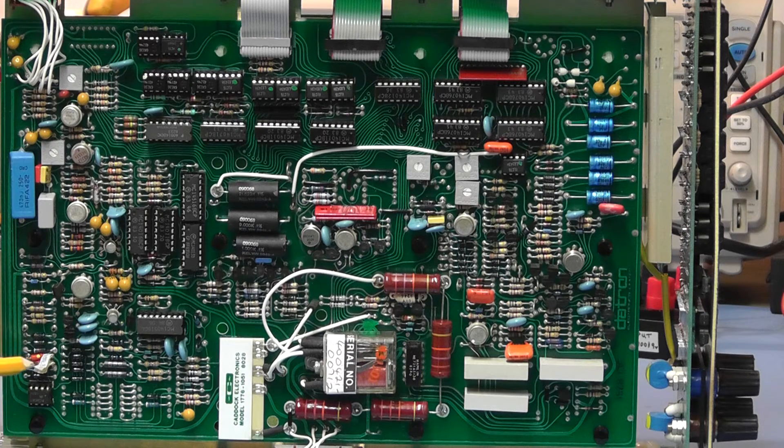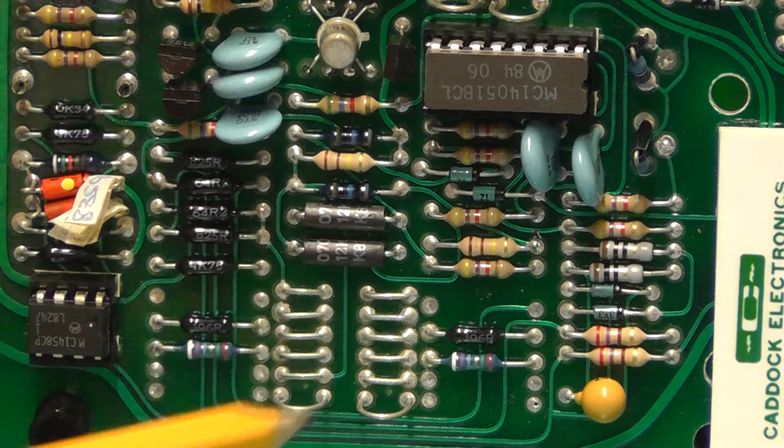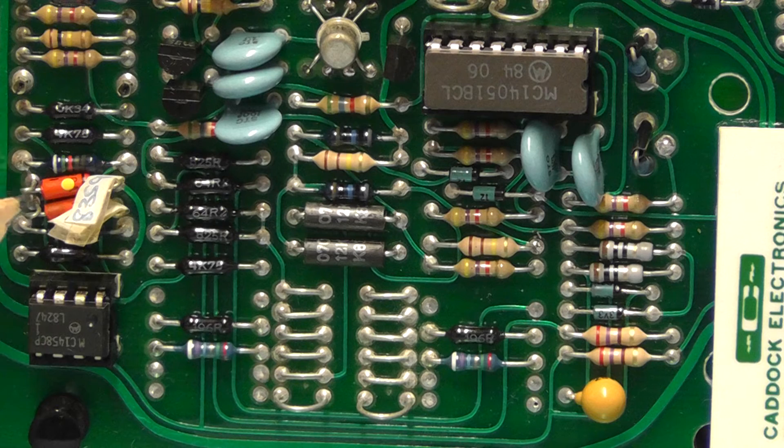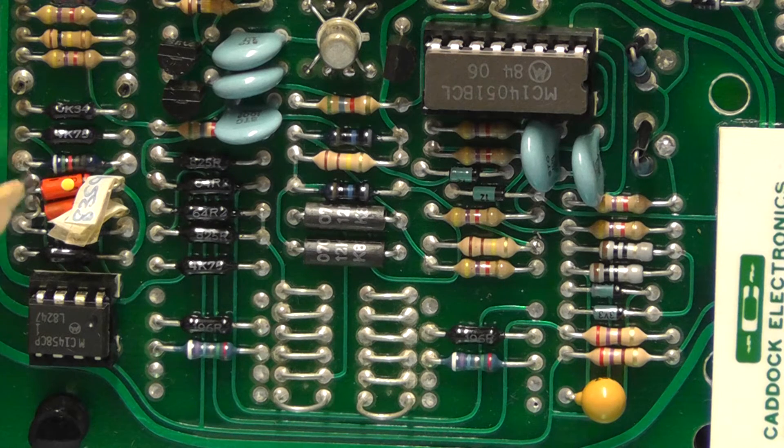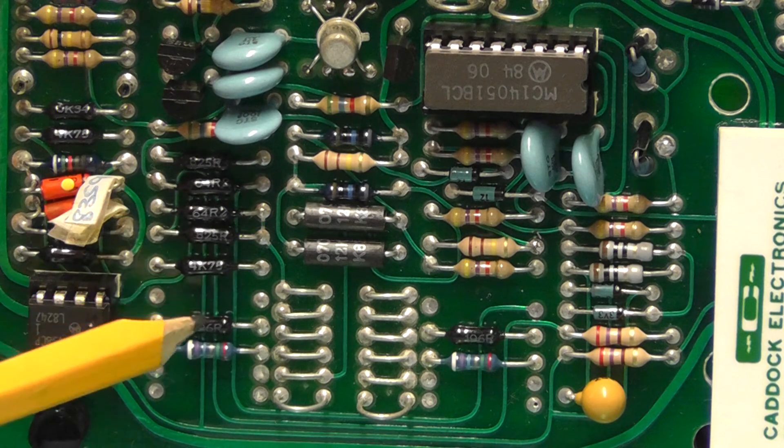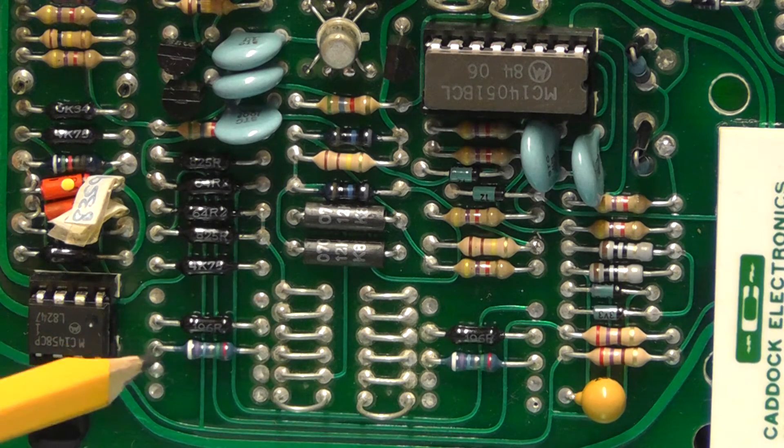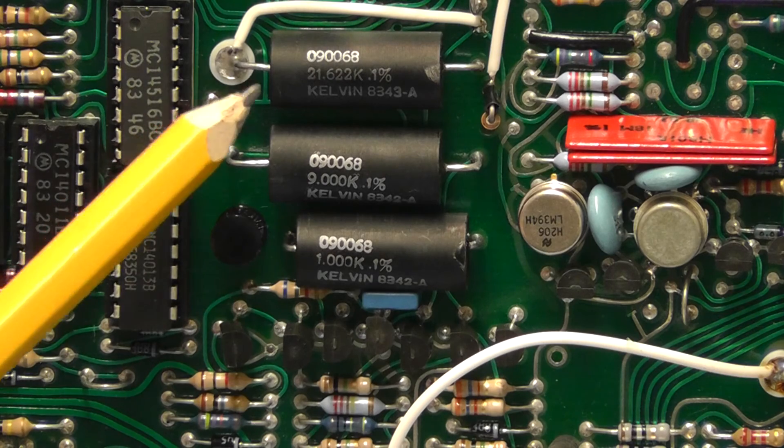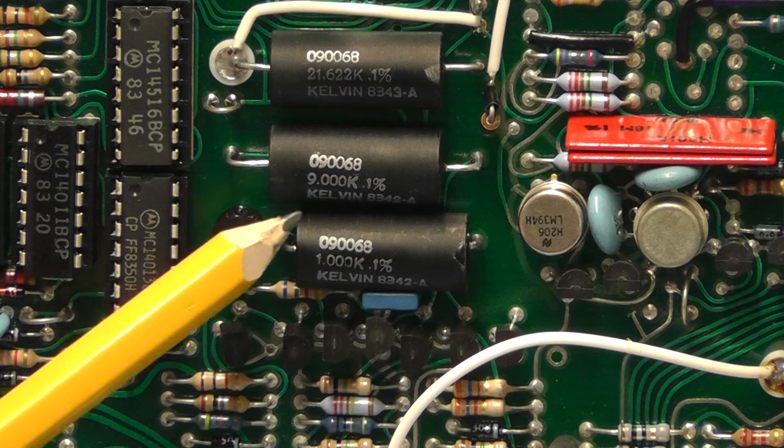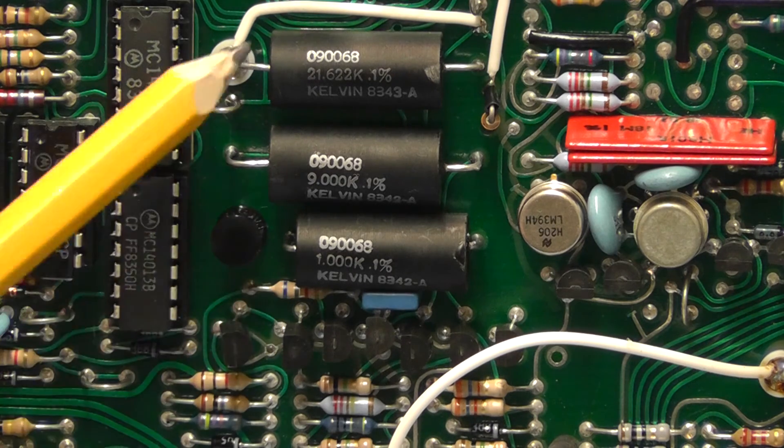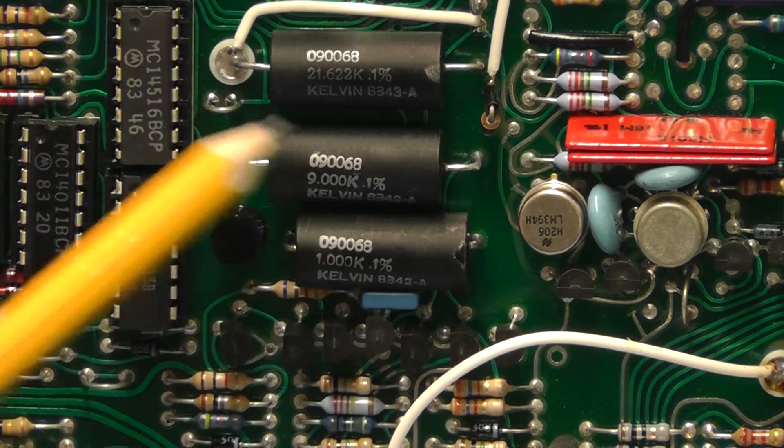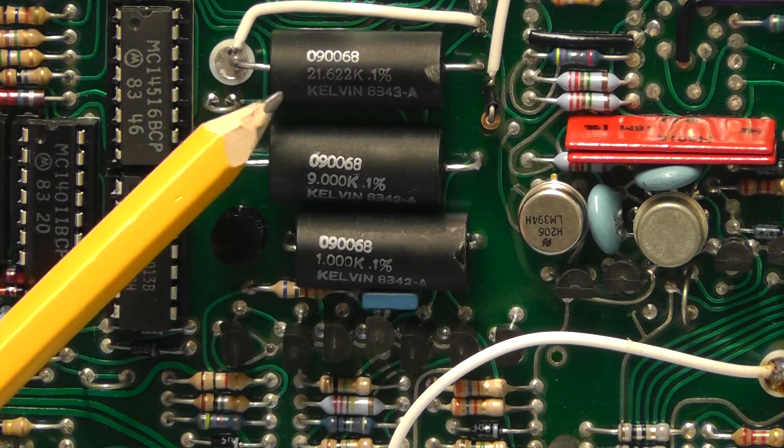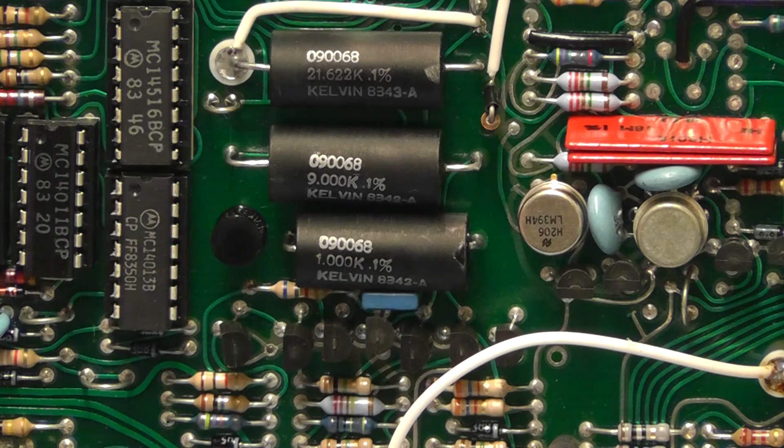I'll just zoom in and have a closer look here at the voltage reference circuit for the meter. Here you can see the voltage reference circuitry on this board. The two orange temperature compensated zener diodes providing the reference voltage, both a negative and a positive reference voltage in this case, and all of the black resistors here are very high stability resistors and they're used together with these shorting links to calibrate the unit during manufacture. In the middle of the board here you can see the resistors that are used to set the gain of the operational amplifier at the input circuitry of the meter. This is used on the different ranges and these high precision resistors, in fact I can read on there it says they're Kelvin type resistors, so very accurate to a few parts per million in terms of a temperature coefficient of those resistors.